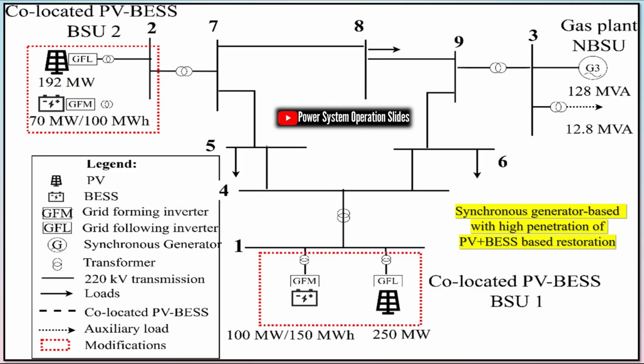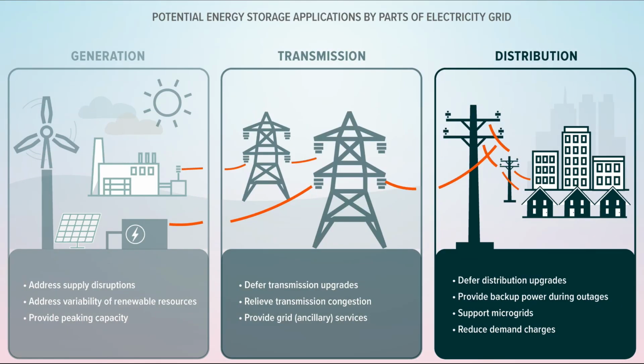During restoration, maintaining a stable system frequency is critical to prevent further outages or cascading failures. Traditionally, small loads are reconnected gradually to avoid sudden frequency dips. However, this cautious approach can slow down the overall restoration process. BESS can accelerate recovery by acting as both a controllable load and a generation source, depending on their charge-discharge configuration. Studies have explored optimal sizing of batteries to provide effective frequency support during restoration.